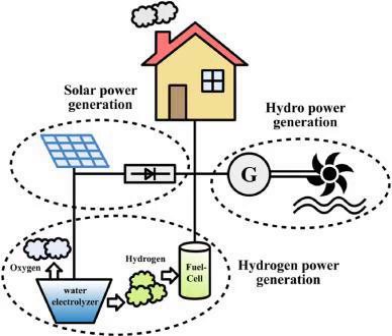System sizing. Based on the resource evaluation and energy needs, size the renewable energy system to match the demand appropriately. Oversizing or undersizing the system can lead to inefficiencies and increased costs. For solar and wind energy systems, use the capacity factor, average actual power output over time divided by the maximum potential output, to determine the appropriate size.